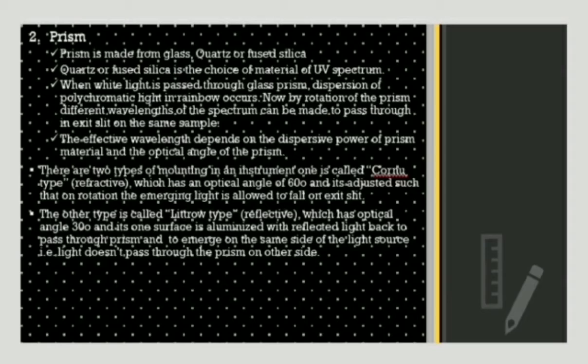Another monochromator used in UV visible spectroscopy is the prism, made of glass, quartz, or fused silica — quartz or fused silica being the material of choice for UV spectrum. When white light is passed through a glass prism, dispersion of polychromatic light into a rainbow occurs. By rotation of the prism, different wavelengths can be made to pass through the exit slit. There are two types of mounting: the Cornu type, also known as refractive, with an optical angle of 60 degrees; and the Littrow type, which is reflective with an optical angle of 30 degrees, where one surface is aluminized to reflect light back through the prism to emerge on the same side as the light source. The monochromatic light then falls on the sample.